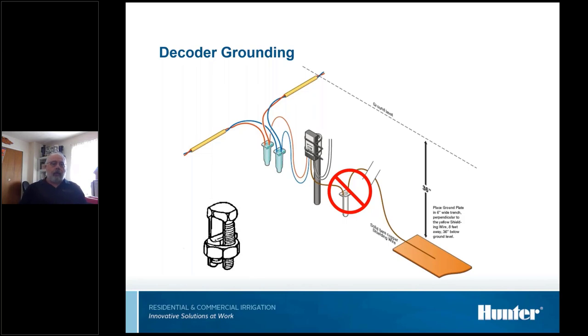Where I cover in the Midwest, we have heavy soils, so our readings are almost always good. That's how you test them. Like I say, it has to be a megger, and that's the kind of readings that you're looking for. So just to clarify, 10 ohms or less. 10 ohms or less is what we're looking for.